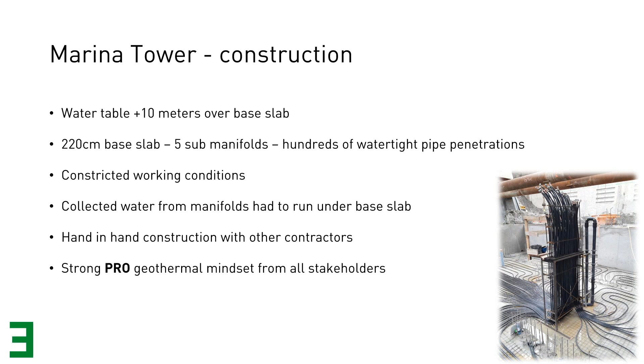The result: the geothermal system now covers 55% of the heating load and 67% of the cooling load of the building. We only installed about 20% of peak capacity and still managed to cover 55% of heating and 67% of cooling. District heating and dry air coolers were used to cover the missing peaks, and domestic hot water is completely covered by district heating, which makes sense.